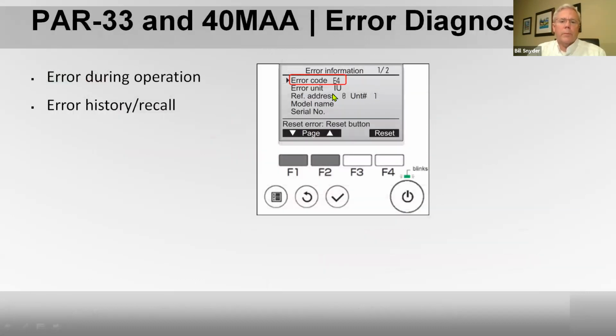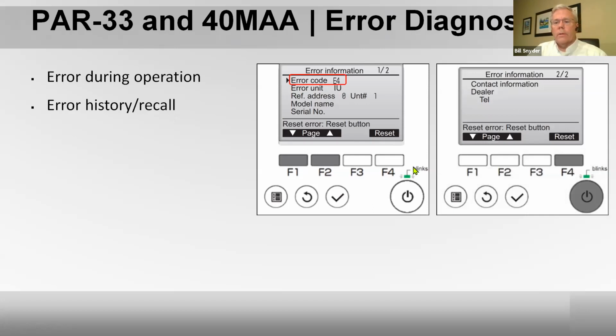Now here's one of the controllers we talked about. It comes right up on the control and tells you error code E4. So hopefully your homeowner or the business owner would call you and say, hey, my unit's not working and the thermostat says there's an error code E4. Error unit IU. Anybody get an idea what that means? It's indoor unit. It could say outdoor unit or indoor unit, but this would be the indoor unit throwing a fault code E4. We'd have to go back, find out what an E4 is and correct it. You're also going to get a blinking light down here. And if you've programmed the information in, it would give a telephone number for you to call. In this case you can't put your name in there, but it will give a telephone number to call and it'll be your shop.